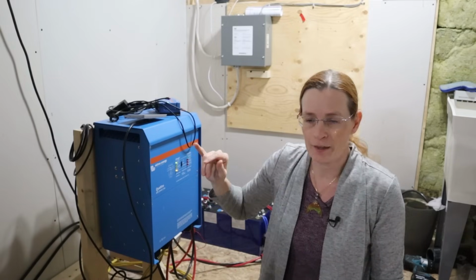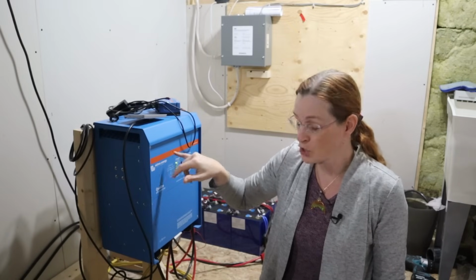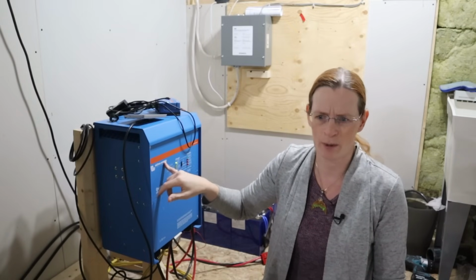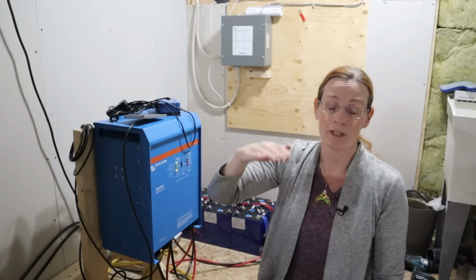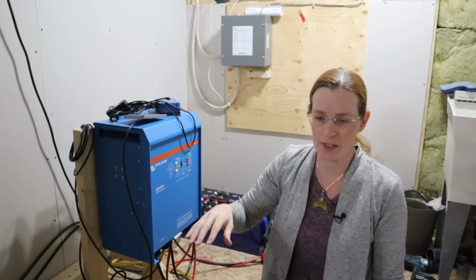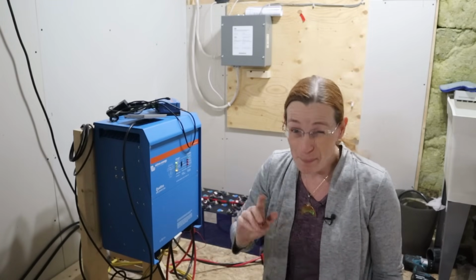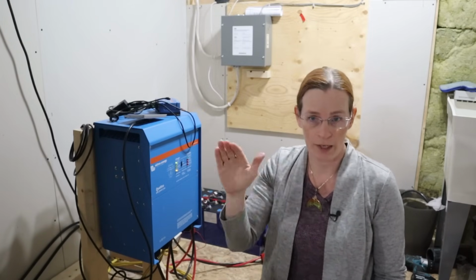So I've got to think a bit more about what I should set for float voltage and float time. I think it's currently set to 1 hour. I might want to keep it like 8 hours while it's up at that high voltage and doing the balancing, so it's got more time to do that. But in any case, for the sake of this test, it's top balanced. Let's go into the BMS first.